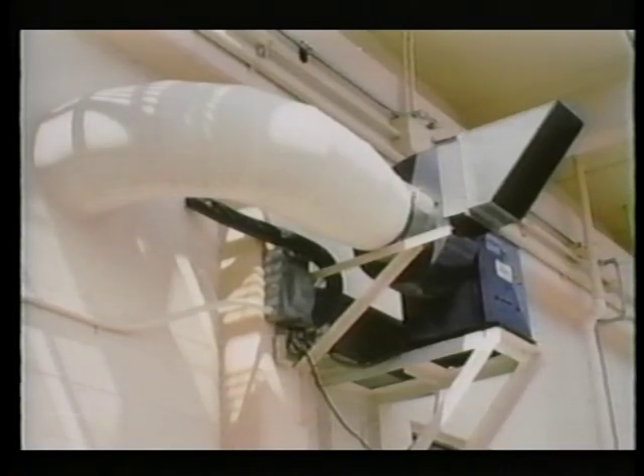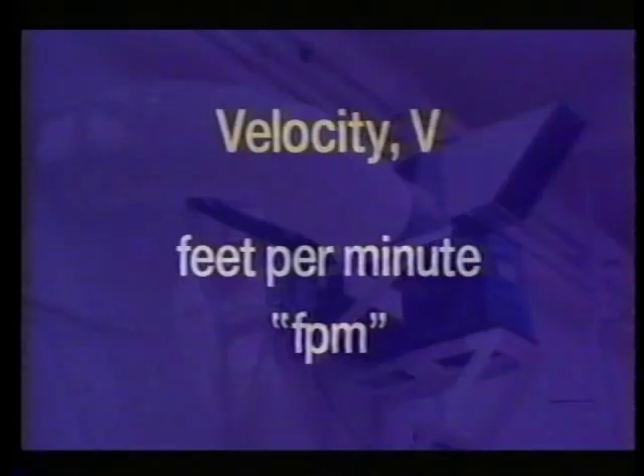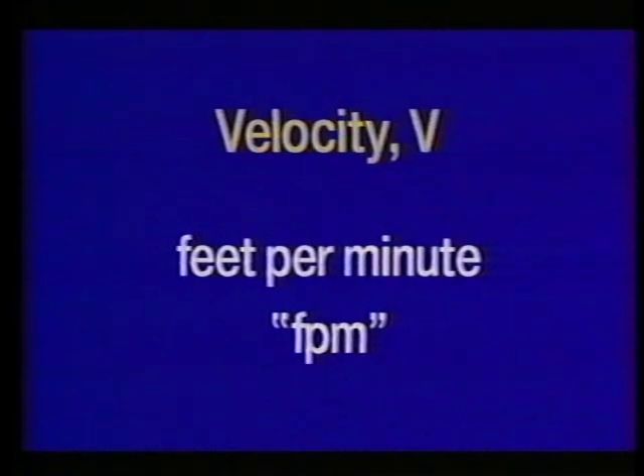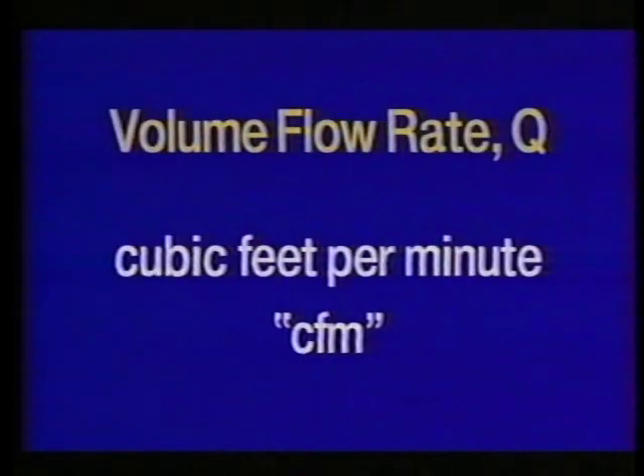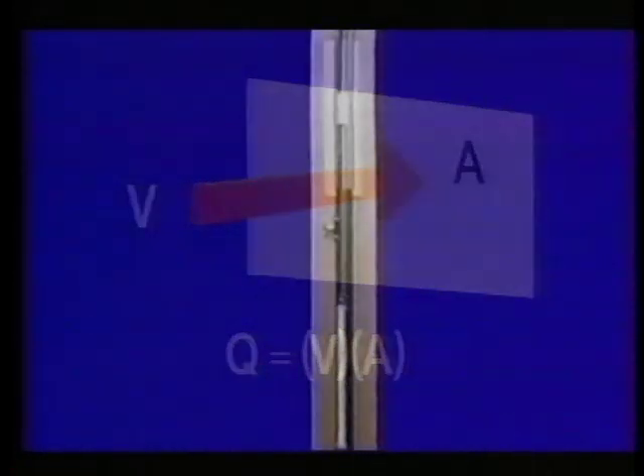If we move 1,000 cubic feet of air per minute through ductwork, we're moving about 75 pounds of air every minute. This requires choosing fans and motors large enough to handle the load. The speed or velocity, called V, of air is measured in feet per minute or FPM. Air volume flow rate, called Q, is expressed in cubic feet per minute or CFM. We cannot directly measure Q; it is equal to the product of the average velocity and the cross-sectional area through which the air flows — that is, Q = V × A.